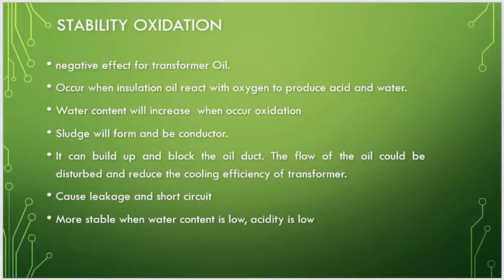Next, for oxidation stability, that will be discussed along with thermal accelerated aging a little bit. Firstly, oxidation is a negative effect for transformer oil, occurring when insulation oil reacts with oxygen to produce acid and water. Water content will increase when oxidation occurs. Sludge will form and be conductive. It can build up and block the oil duct. The flow of the oil could be disturbed, reducing the cooling efficiency of the transformer and causing leakage and short circuit. The oil is more stable when water content is low and acidity is low.